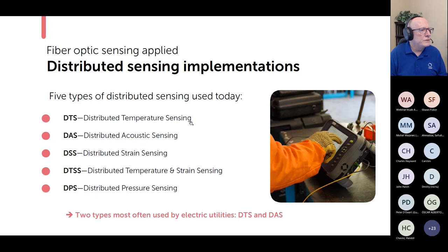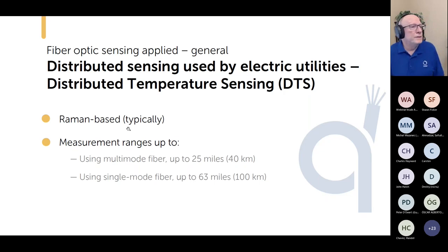So the five types: distributed temperature sensing, distributed acoustic sensing, meaning sound, distributed strain sensing, effectively tension, distributed temperature and strain sensing. We'll talk about why these are talked about separately, and distributed pressure sensing. Of these, the first two, DTS and DAS, are by far the most common for electric utilities today. So distributed temperature sensing is up first. This is based on Raman backscattering, typically, and you can go really long distances, depending upon the fiber type that you're using. So you can effectively cover a typical transmission line, no problem.